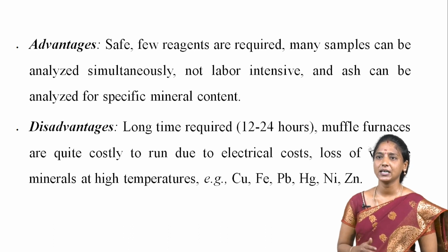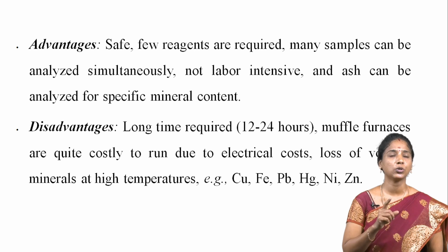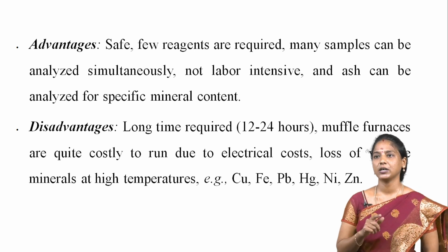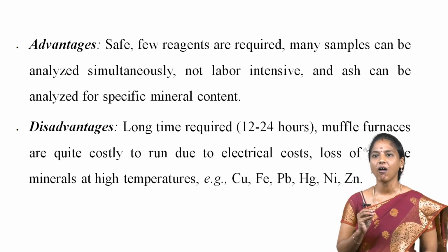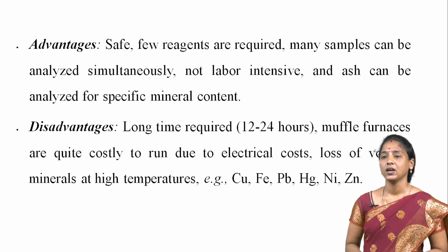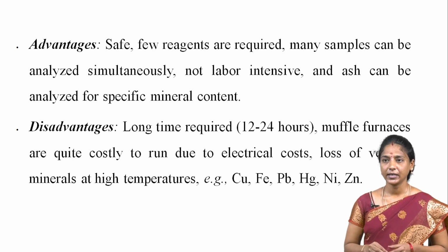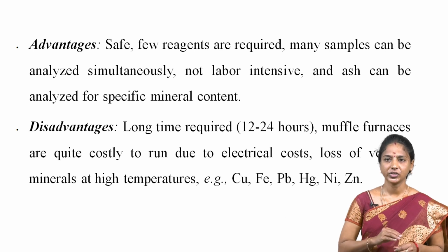These are the disadvantages. A long time is required, a duration of 12 to 24 hours. Muffle furnaces are quite costly to run due to the electrical cost. Loss of volatile minerals at high temperature, for example copper, iron, lead, mercury, nickel and zinc.